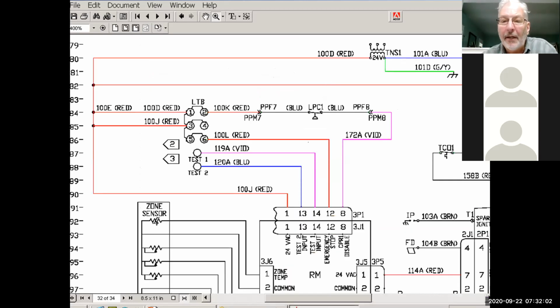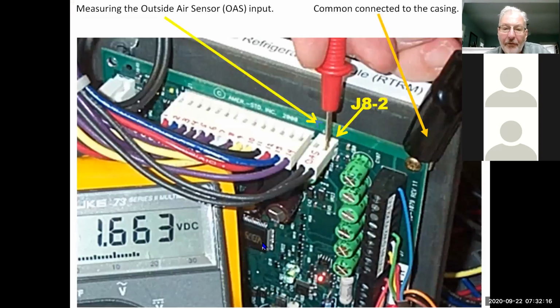And this is just a little close-up of that to show that we do feed these boards from different locations. It's not just one wire that feeds that main board. All right, so on the board, here's that red wire right here. As you can see, these pins are a little small too, so you're probably going to need needle points to get in there to get any kind of good voltage readings. But these are going to be your inputs and outputs. So there's your 24-volt hot and common to feed the board, and then you've got your pressure switch wires in here, your safety switch wires. You've got other circuits in here which we'll touch on later.